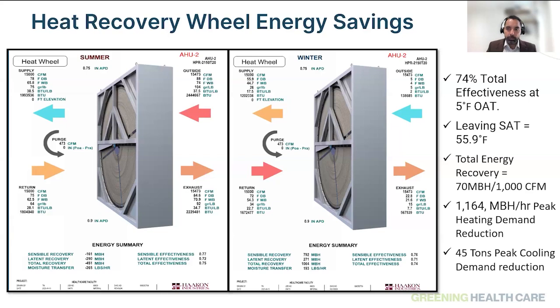We talked about retrofitting these units, and why enthalpy wheels are one of the important elements in those is because they not only help you recover the waste heat from the exhaust, but also help you lower your peak heating and peak cooling demands as well. So as an example, for a 15,000 CFM unit, you could reduce your peak heating demand by almost 1.1 MMBH in the heating season. And similarly on cooling demand, you could reduce your cooling demand by 45 tons for a 15,000 CFM unit.